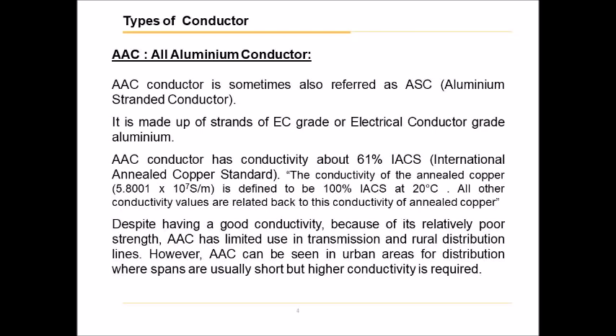AAC, all-aluminium conductor. AAC conductor is sometimes also referred to as ASC, aluminium stranded conductor. It is made up of strands of EC grade, or electrical conductor grade, aluminium. AAC conductor has conductivity about 61% IACS — International Annealed Copper Standard. The conductivity of annealed copper is defined to be 100% IACS at 20 degrees Celsius, and all other conductivity values are related back to this conductivity of annealed copper.